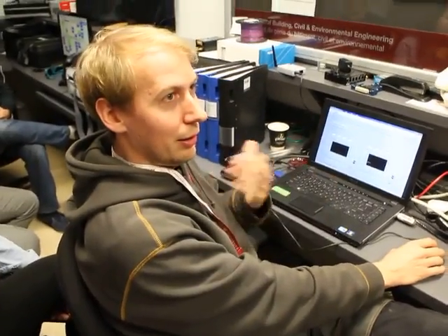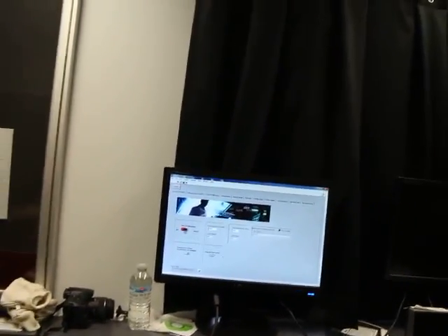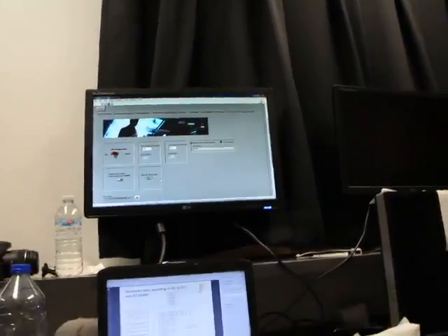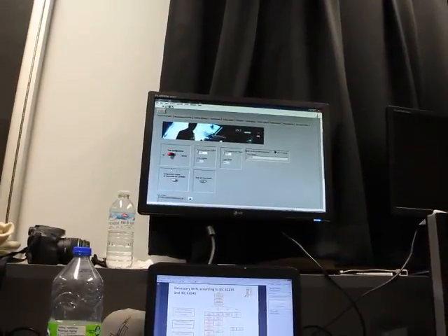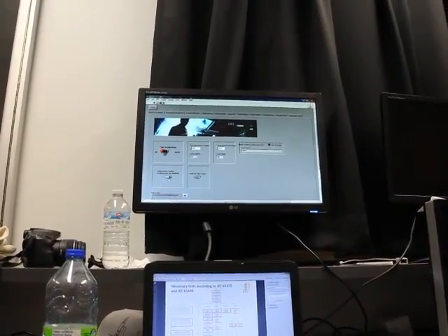But maybe we also talk a bit about what happens if we have a closed loop circuit. Just for you to know what is happening, what you would do then is turn that off, press that button, because we have a closed loop circuit. We don't suck the air from the room. Somehow it is also from the room, but it's a closed loop circuit, right? What you could also do then is set a temperature, because then you can set the temperature at the inlet of the water-air heat exchanger.